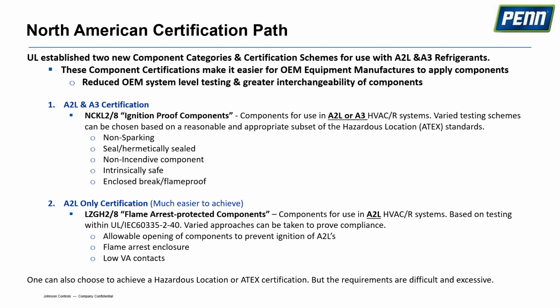There are really three ways here. The first is making sure the openings to any ignition source are small enough that the refrigerant can't reach it. That's what Anna and I talked about regarding electronic controls. Some electronic controls use relays with small vent holes; if small enough, refrigerant molecules typically can't reach the ignition source. The other alternative is to use sealed relays, ensuring there are no openings and the refrigerant has no path to that ignition source.